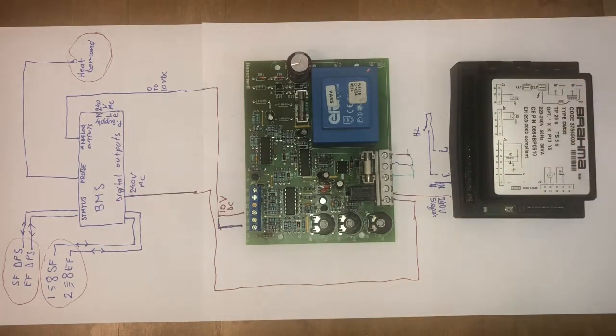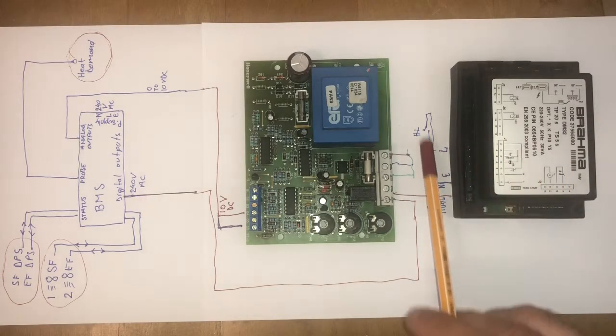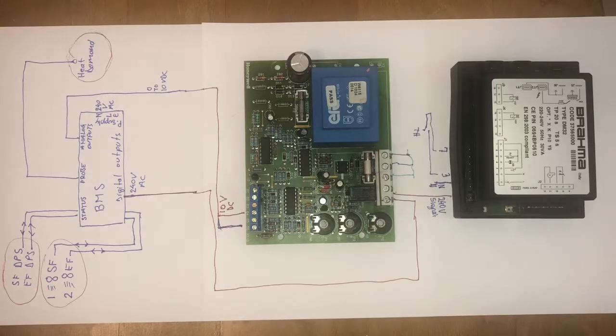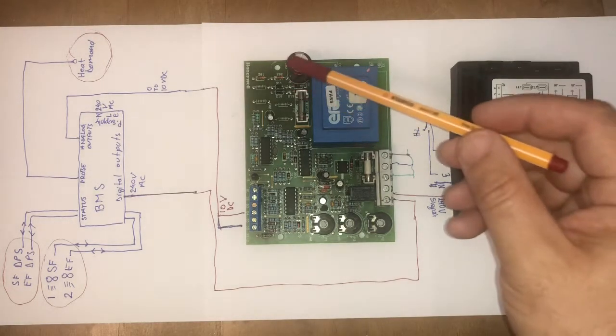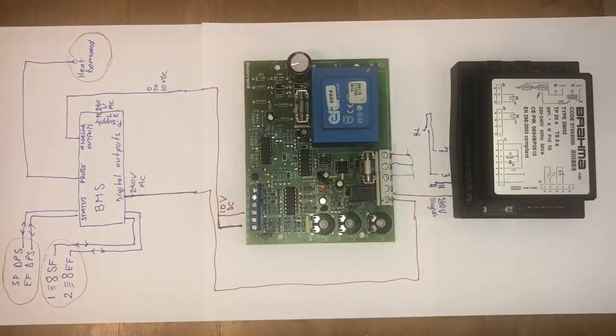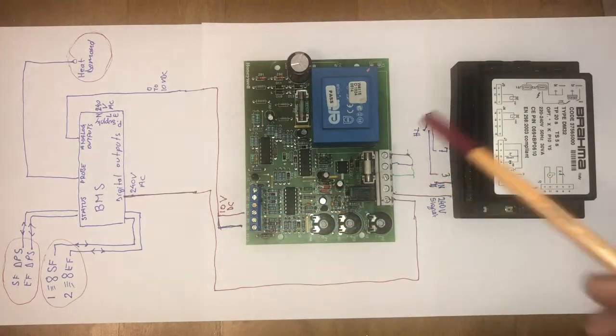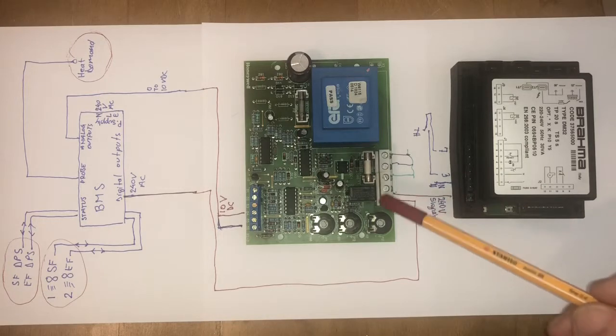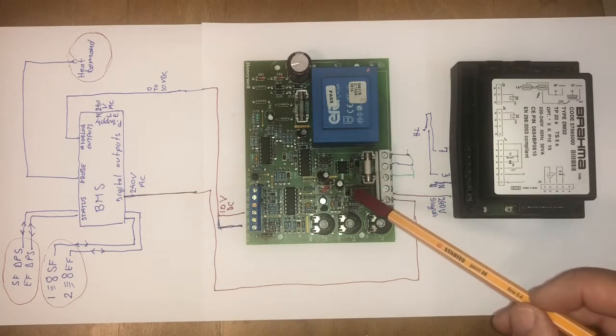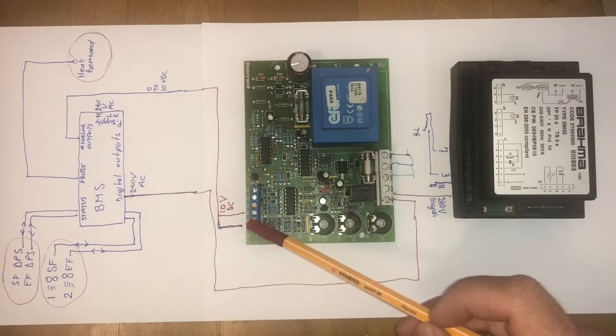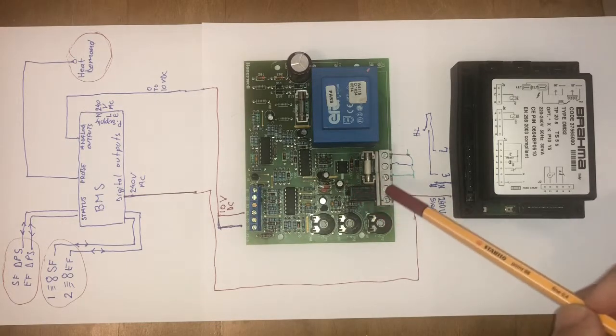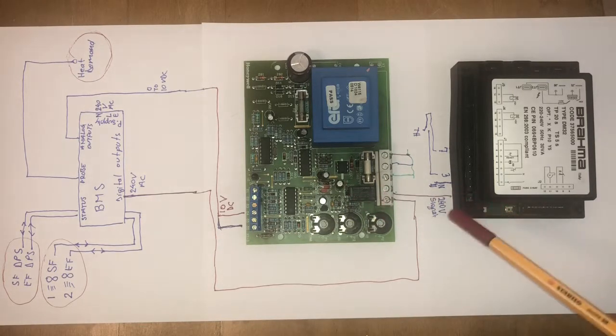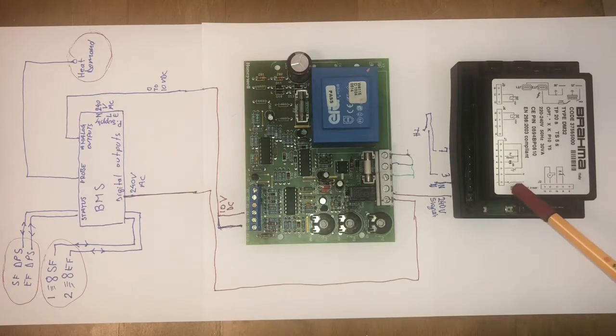So this Brahma controller received now has live and neutral, it's alive, and then this thermostat is open, so the Brahma controller is not initiating itself. So this board now has 10 volts here, the power supply is okay, 240 volts, and this relay is closed because when I applied the signal of 10 volts, this relay just closed the circuit and the electricity continues its journey, and the Brahma controller got the power supply, but I have an open thermostat.